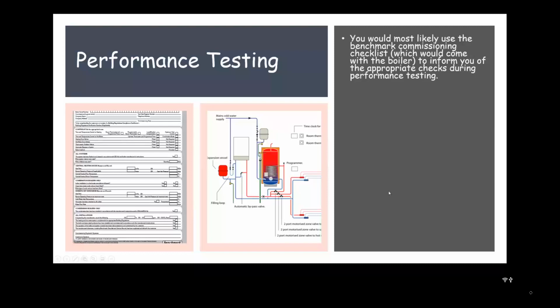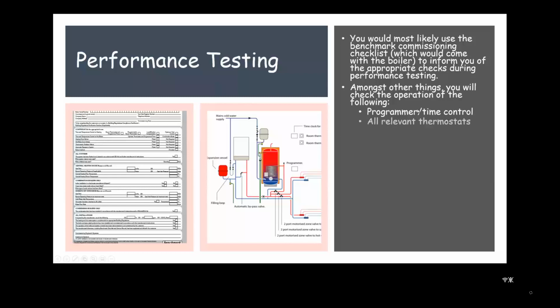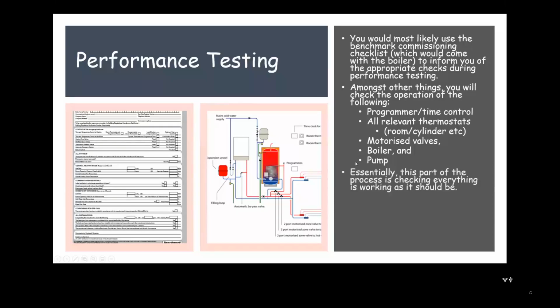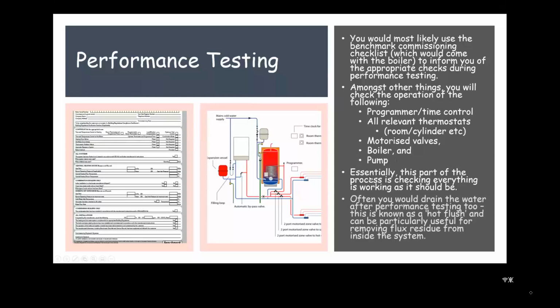The performance test is essentially just checking everything's working the way that it should. You can use the Benchmark commissioning checklist to help with that, which would normally come with the boiler. So some of the things you check: the programmer or time control is working as it should. The relevant thermostats are switching the system on and off as required. The motorized valves are opening and closing as they should in relation to when the room stat or cylinder stat start calling for heat. Check the boiler's firing up and the pump starting and circulating as it should. Essentially, it's checking everything is working the way that it should be.